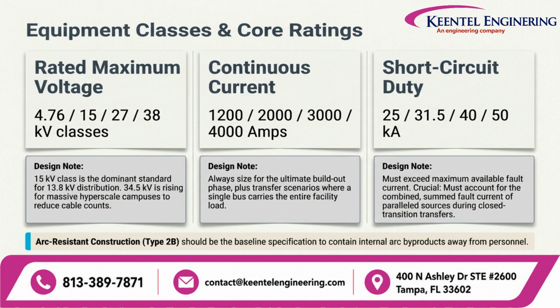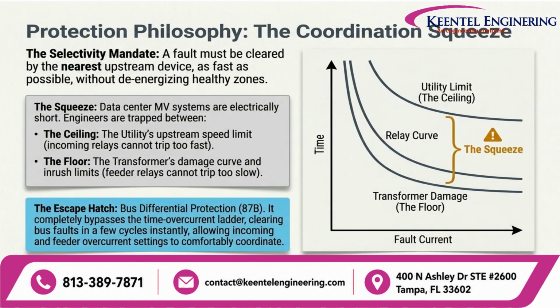This includes voltage and current ratings, as well as short-circuit duty, which must account for the summed fault current of paralleled sources. Arc-resistant construction should be the baseline for personnel safety. Coordination can be a challenge in electrically short systems. Engineers must balance utility speed limits with transformer protection curves. Bus differential protection provides an important escape hatch by clearing bus faults instantly, bypassing the usual time-current coordination limits.